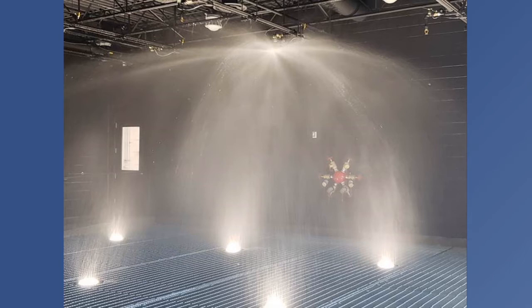All right, let's get into the questions here. First of all, Shaun, the first question is that this individual is protecting a room that has a dimension of about 13.5 feet by 25 feet or a little bit more. Does Viking even offer a sprinkler that can cover this kind of area? Yeah, we offer a sidewall sprinkler, our VK460 as shown behind us, that has a coverage area of up to 14 by 26 feet. When you're looking at a pendant sprinkler, the maximum coverage area you can have is 20 feet by 20 feet.